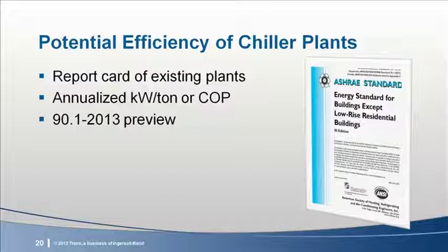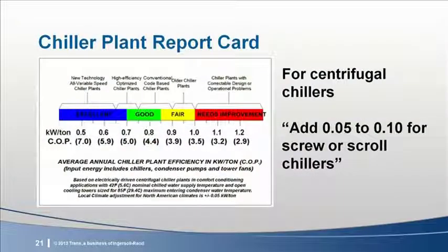Now, one way to think about how well your chiller plant operates is by some sort of a report card. Here's one that Tom Hartman came up with years ago. While the units are kW per ton, the fine print shows that this is an annual number. He doesn't say exactly how to calculate it, but he does give some guidance about the kinds of instrumentation required for collecting it. The performance scale suggests you shift the numbers slightly higher if you're using water-cooled screw or scroll chillers, because these chillers are generally a little less efficient, although we'll see in a moment that the gap is narrowing.